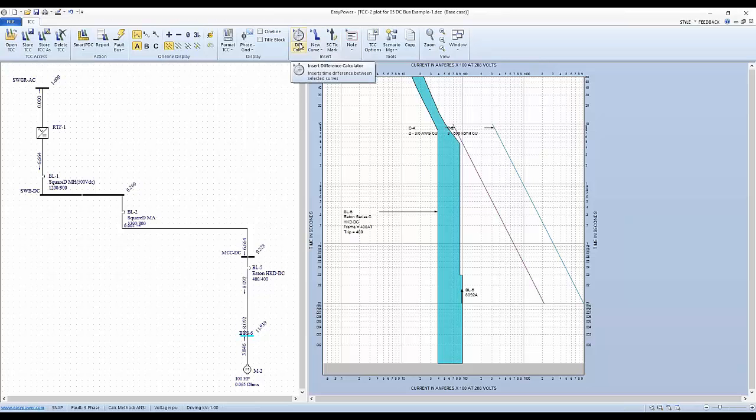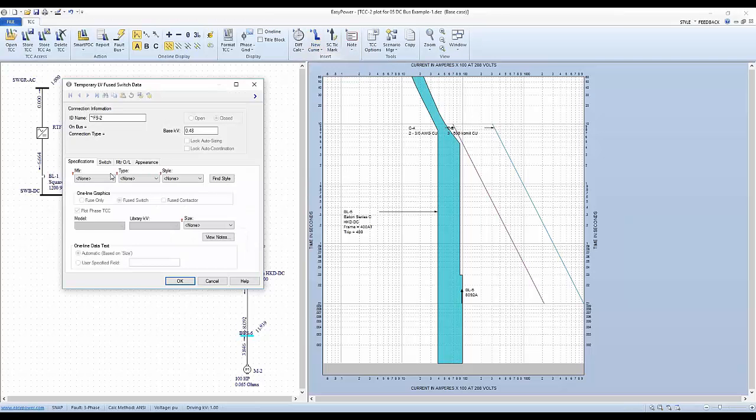and at that point what I would suggest is I go in and I try to utilize a new curve, and we can say try out a low voltage fuse that we could see if, well, would a fuse work better in this situation. And let's say we have a 350 amp load.